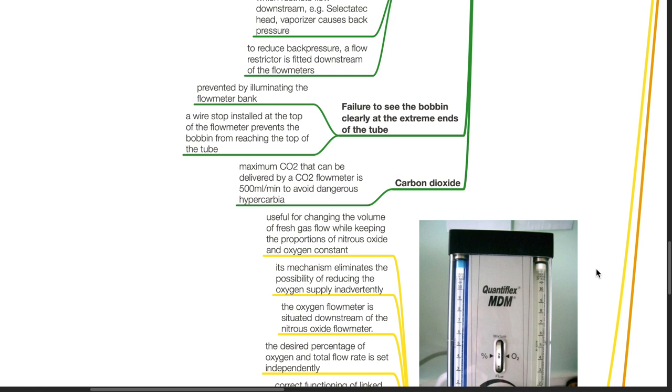Carbon dioxide: Maximum carbon dioxide that can be delivered by a carbon dioxide flow meter is 500 mls per minute to avoid dangerous hypercarbia.